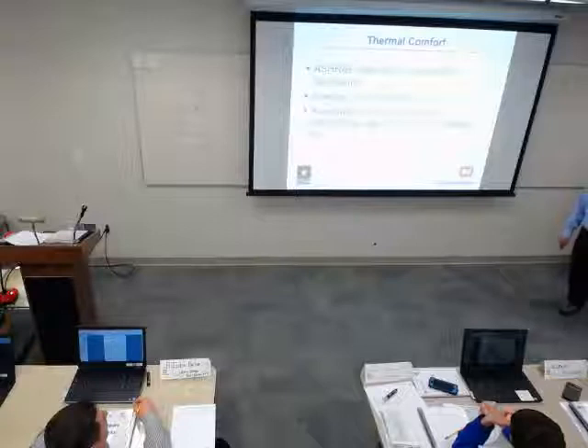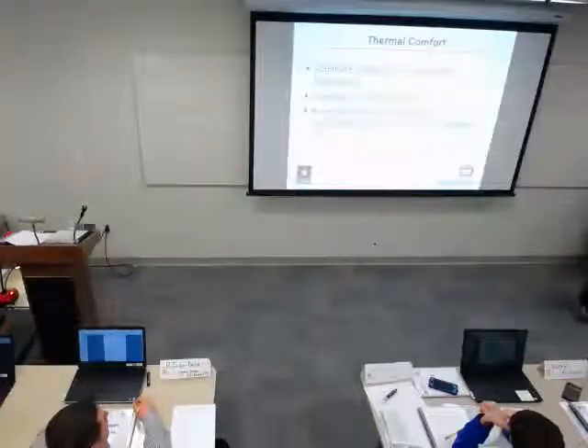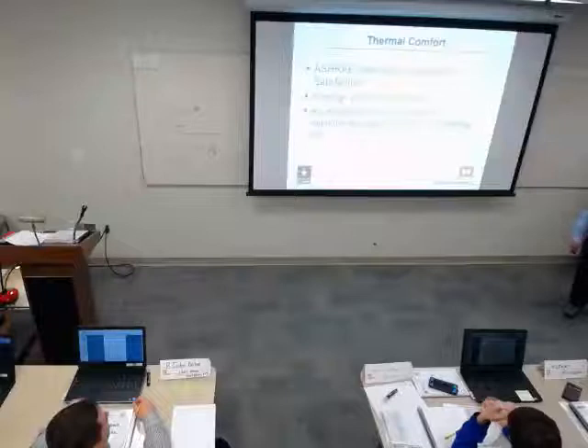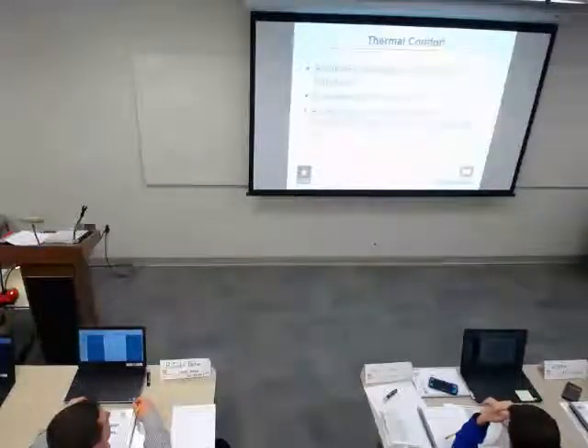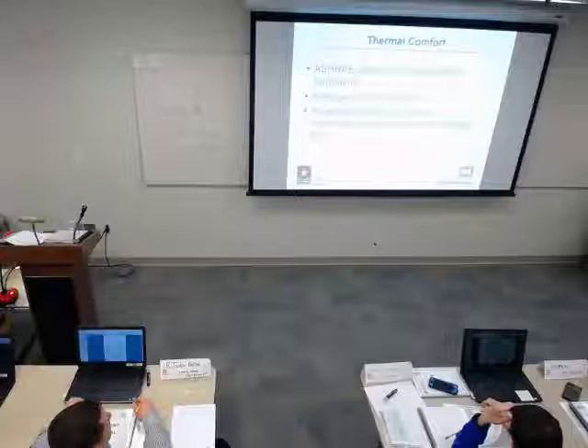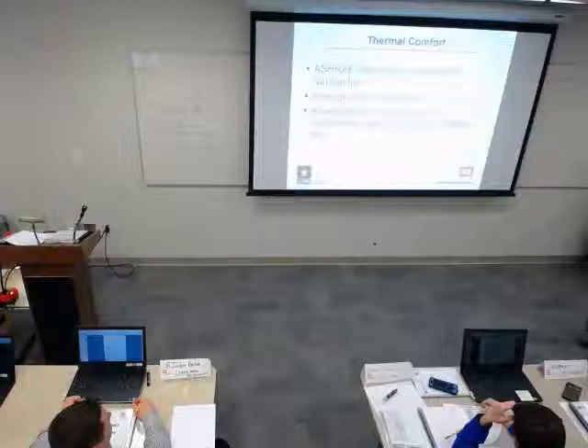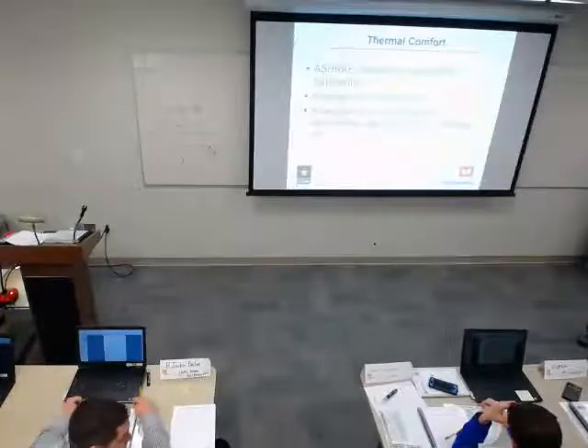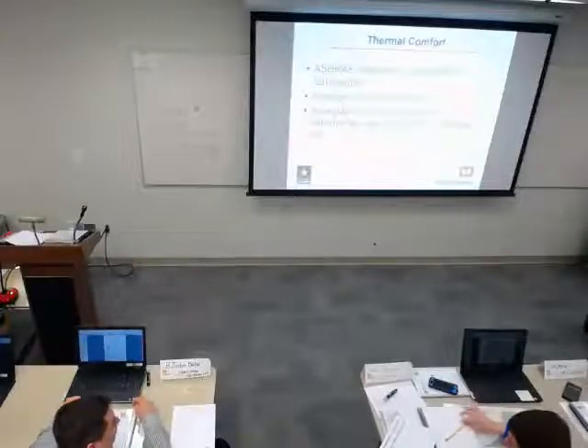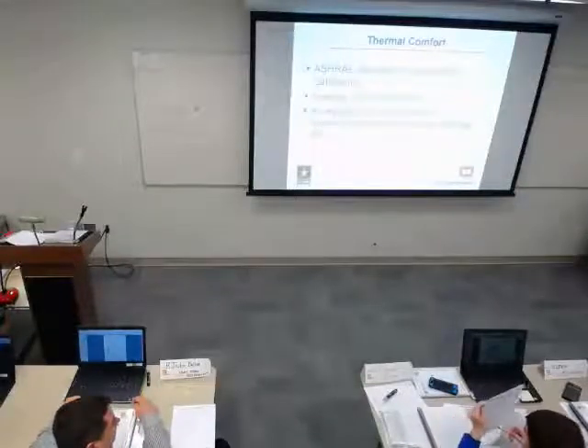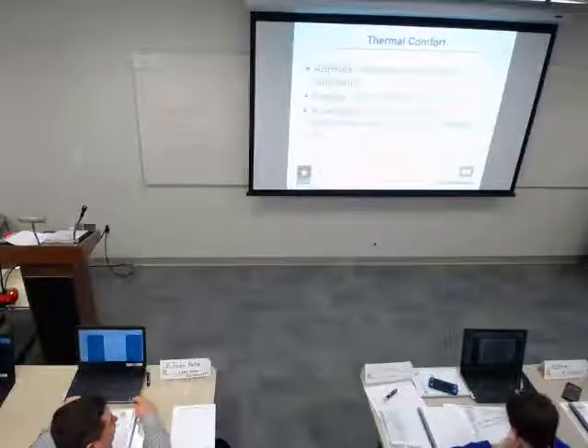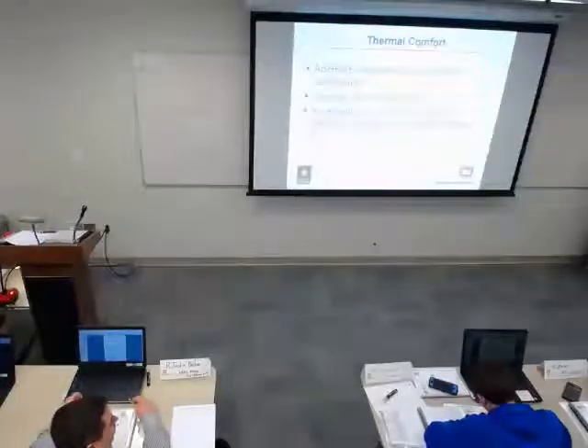ASHRAE Standard 55 is a standard that addresses thermal comfort. And the conclusion is that you're doing well, you've met the criteria, if 80% of the people are satisfied. That means 20% aren't. And I'll level with you. In my experience as a designer, I have never, ever had people come to me and say, we're really happy because 20% of our people are not. But as an overall standard, that's considered pretty good. A lot of work was done with this.